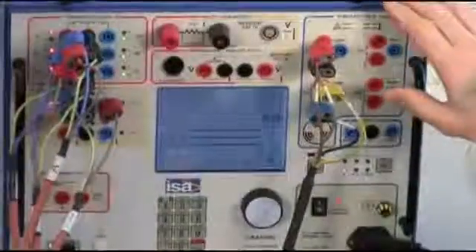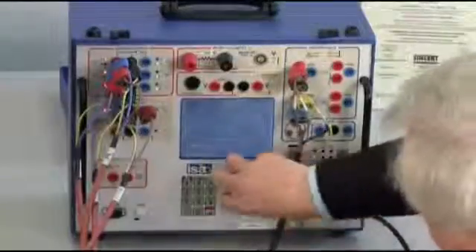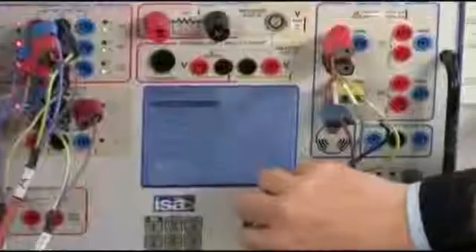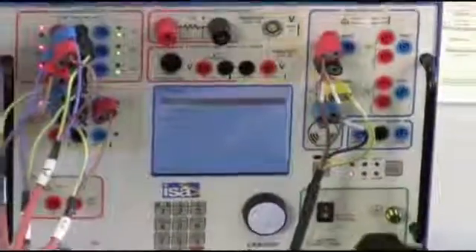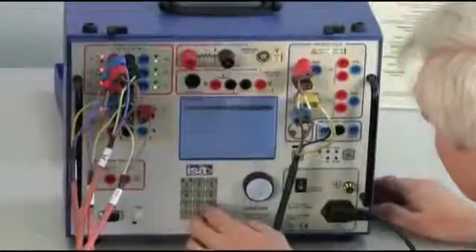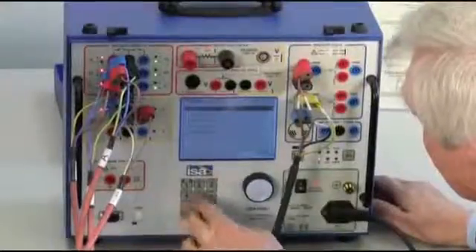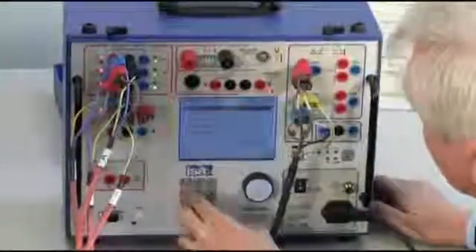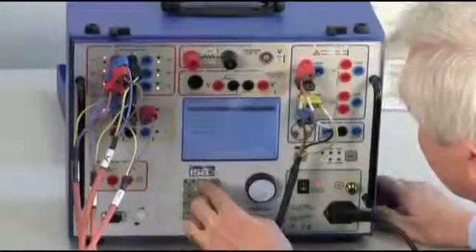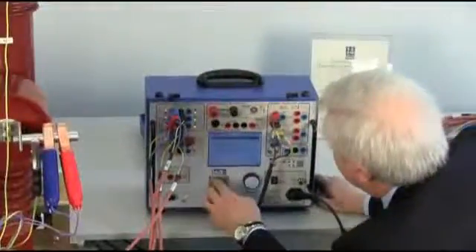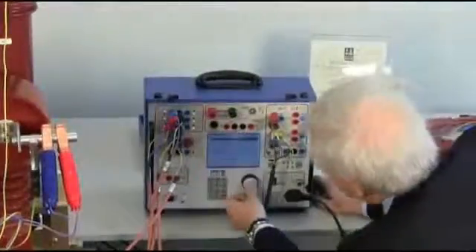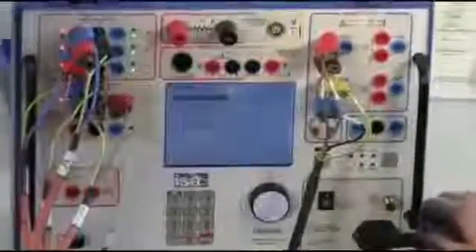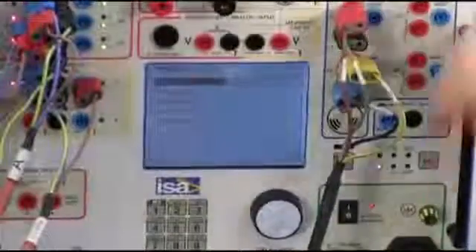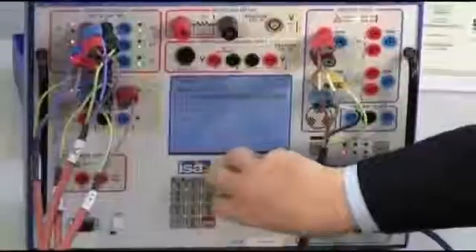Now you can just go to the menu and save result. As you enter here, you have the possibility to give a name to your test. So it is test 1 or test open, close, sorry. Okay, and I say for instance 1. Okay, as I press, the result is saved into the memory of the test set. So later on we will download it to the computer.